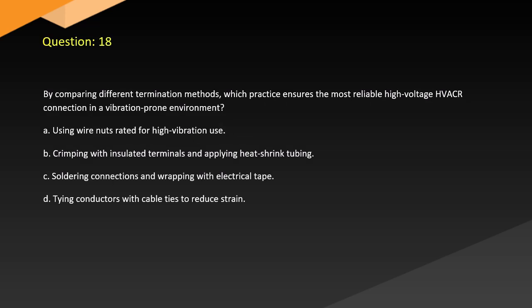Question 18. By comparing different termination methods, which practice ensures the most reliable high-voltage HVACR connection in a vibration-prone environment? A. Using wire nuts rated for high vibration use. B. Crimping with insulated terminals and applying heat shrink tubing. C. Soldering connections and wrapping with electrical tape. D. Tying conductors with cable ties to reduce strain.